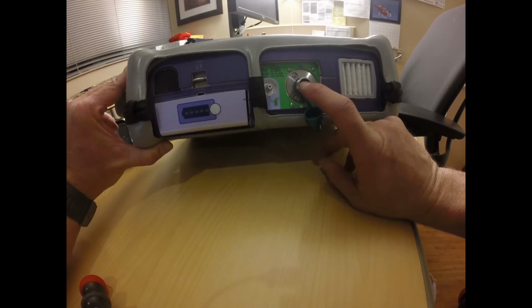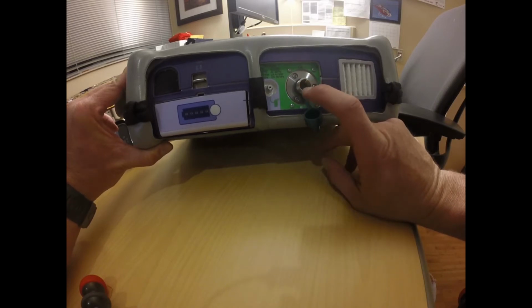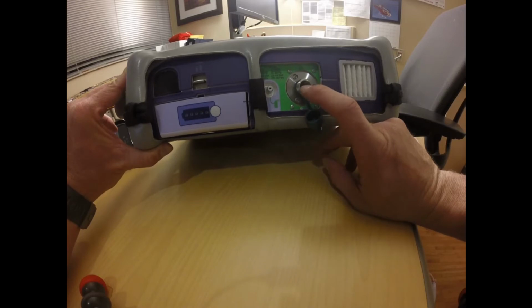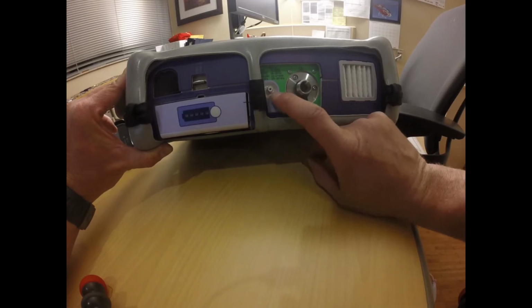Also on the side of the ventilator is a couple of very important pieces. Right here is where my high flow oxygen hose is screwed into, or if I choose to use a low pressure setting to deliver flow or oxygen to my patient, I can screw a Christmas tree into that and use an oxygen extension tubing for that. And then here is where I'm going to use oxygen extension tubing to plug into nebulized medication if I wish to use the ventilator.